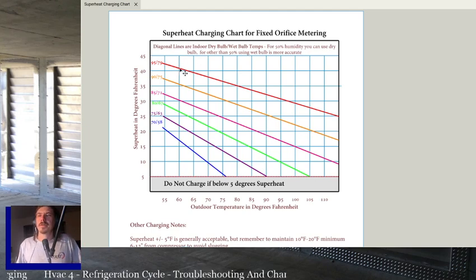What you're gonna have here is outdoor temperature on the bottom, and superheat on the side. So if you're charging a fixed orifice, you'll find your outdoor temperature, and then you'll find your indoor temperature. Notice we got two numbers here. The diagonal lines are indoor dry bulb and wet bulb temps. So the first number is dry bulb, second number is wet bulb.